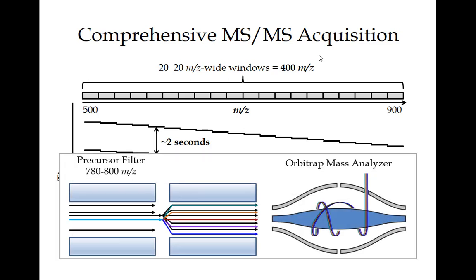This is what it would look like inside a Q Exactive. You've got this quadrupole filter set for a given window, and unlike an SRM experiment where you're only letting in a very specific ion through a ~1.7 m/z window, here we're letting in 20 m/z, so multiple precursors come in. Each precursor generates fragments, and you acquire this mixed fragmentation spectrum. This is done on a full-scan mass analyzer — in this case an Orbitrap.